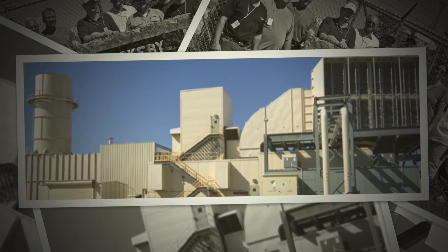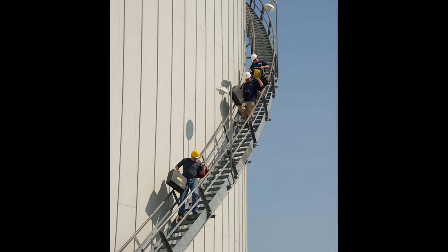Rokeby Generation Station found an innovative way to integrate technology from another industry to improve the output capacity and efficiency of its combustion turbine. To increase summer generating capacity when it's most needed, LES engineers designed a first-of-its-kind system to increase the unit's output by cooling the turbine inlet air before it entered the combustion turbine. This increases the efficiency of the unit with no additional fuel costs. The ice storage inlet air cooling system served as a model for other sites around the world.